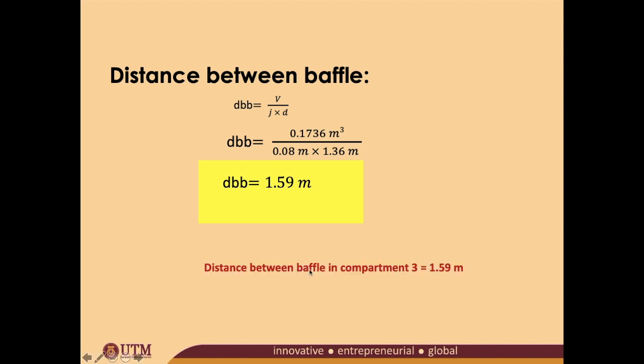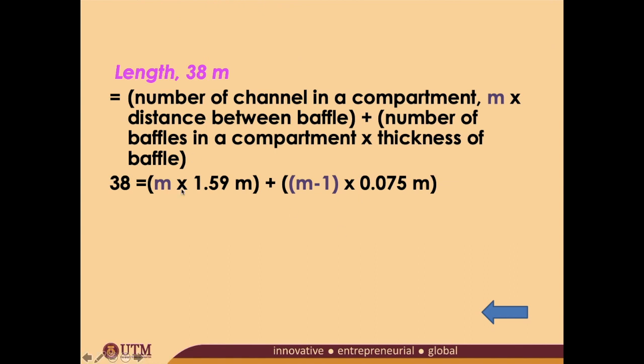Therefore, the distance between baffles in compartment 3 now is bigger size - there's wider spacing which is 1.59 meters. Doing for the last time to find out the number of channels. Now the distance between baffles has changed again and it is 1.59 meters. We solve this equation and we will be obtaining a value of M to be 22.9 or 23.